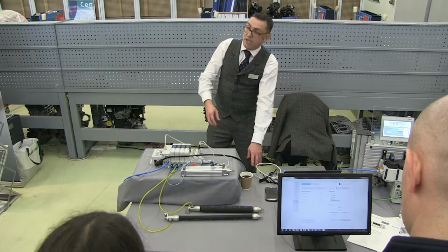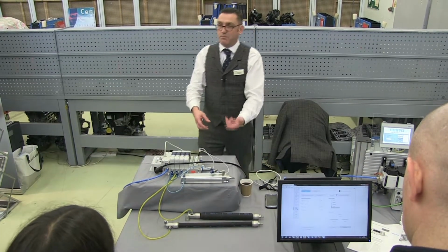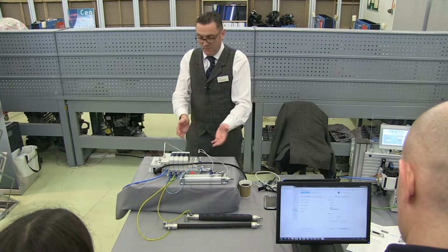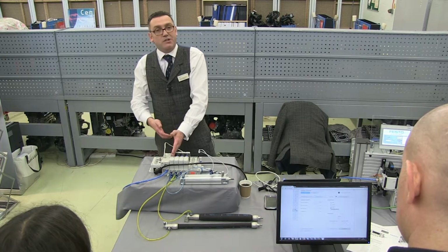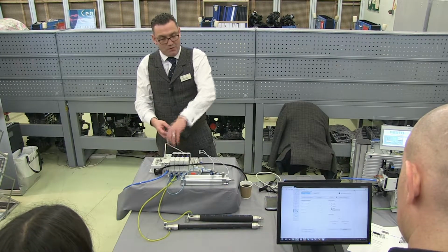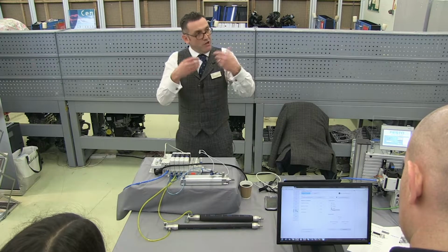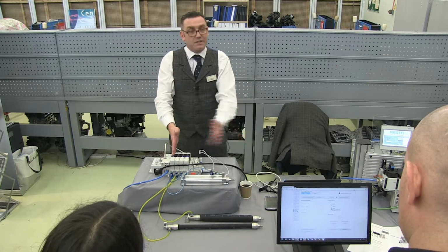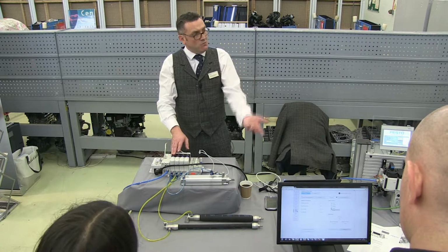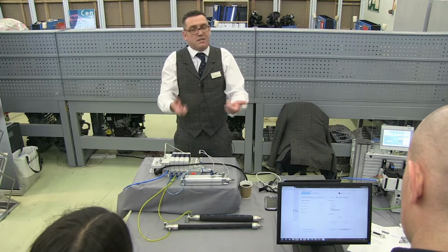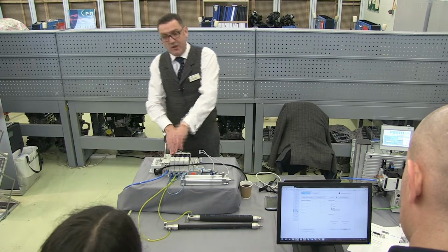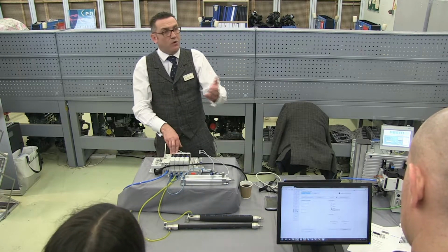I could change the pressure, it will compensate for the pressure as well. Inevitably we get to a point where it can't compensate anymore. One of the apps we have is a leakage detection app. So what I can do when the machine's brand new is I can run a reference move on it, and what it'll do is it'll analyse the cylinder and it'll say, under normal circumstances, this is my typical leakage rate on this particular valve.